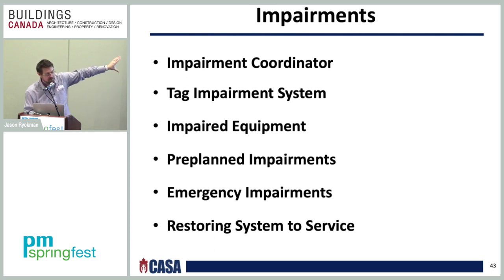You have to have a tag impairment system in place. You have to figure out your impaired equipment, what they are, pre-planned impairments, know the difference between pre-planned impairments, emergency impairments, and restoring the system back into service. So a formal impairment program establishes procedures for maintaining the system control valves in the correct position. Furthermore, implementation of an organized impairment program can also minimize the length of time that a system is out of service. This chapter, chapter 15, provides the basic requirements for such an impairment program.